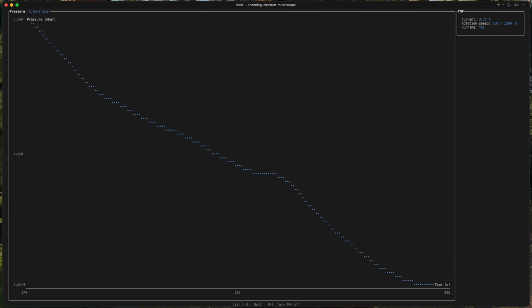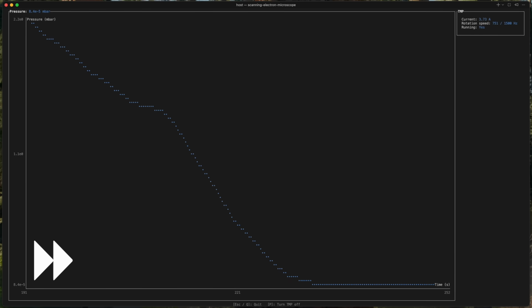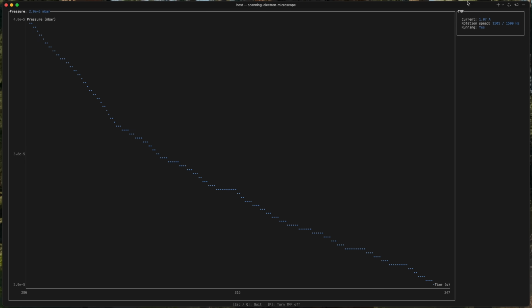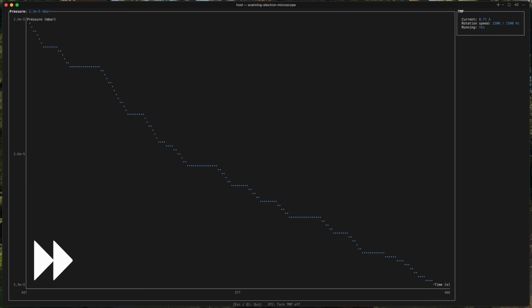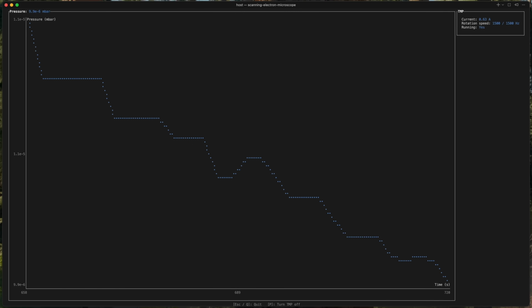After 3.5 minutes, the pressure is dropping so fast that the graph is useless again. We're at 2 times 10 to the negative 4 millibar, and the turbo is only at 50% of its target rotation speed. After 5 minutes, the turbo has reached its target rotation speed. The pressure is an order of magnitude lower at 2 times 10 to the negative 5 millibar, and it's still dropping. After 12 minutes, we're into the 10 to the minus 6 millibar range, and the pressure is still dropping. This should be good enough for an electron microscope, so let's leave it here.